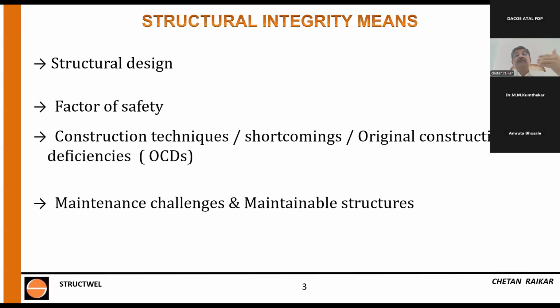Constructed -- I'll go back to the design, on the drawing board. No architect, no structural engineer is aware of maintenance and maintainability of different components of a structure. They give a duct which is only 1.5 feet by 2 feet and has 6 pipes in it. How does one replace a pipe? How does one even go inside? And then they put an RCC grill outside as a permanent feature, so no one can get into it. If the pipeline starts leaking, you have to break the RCC grill just to maintain it.